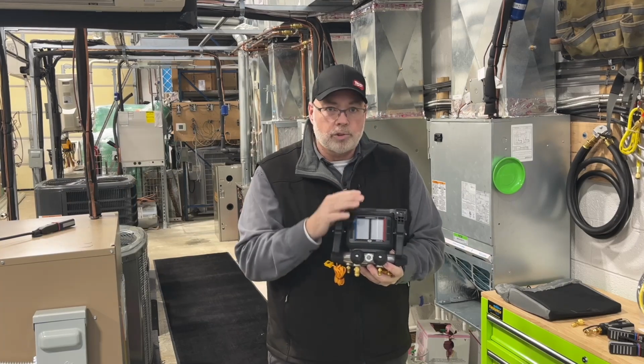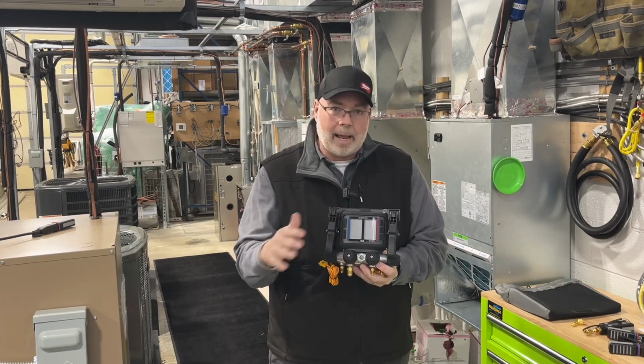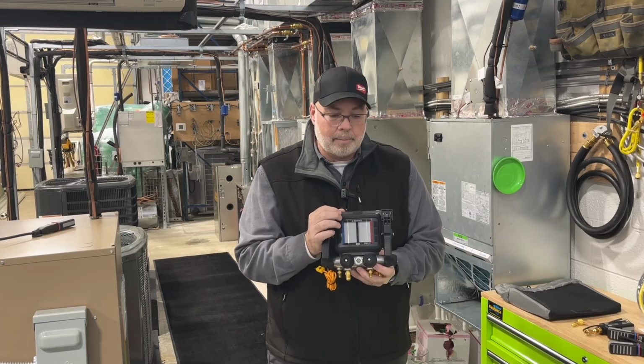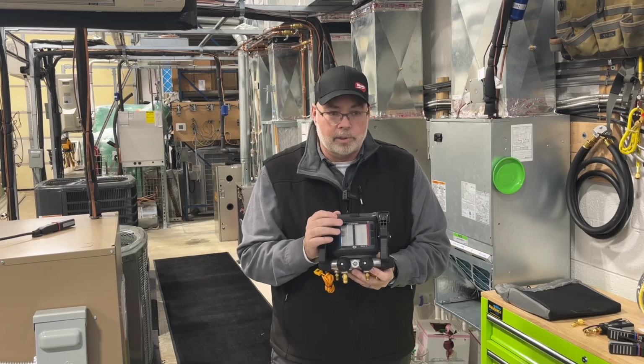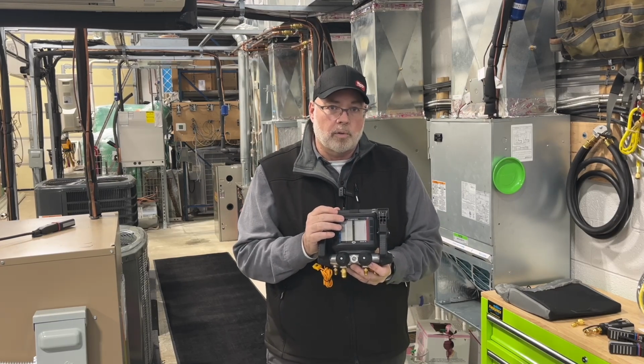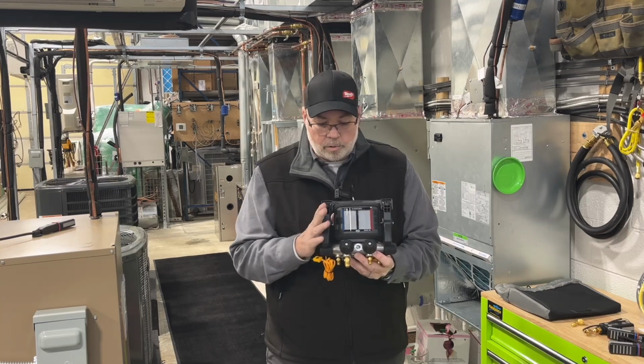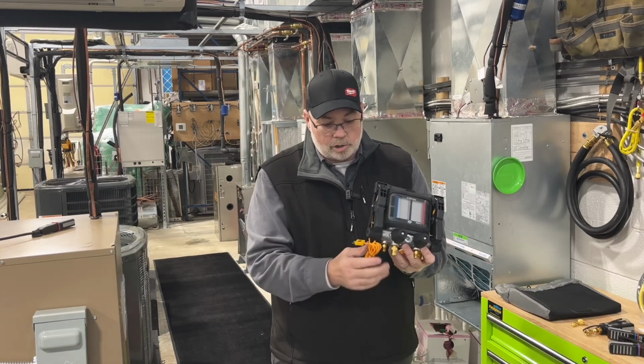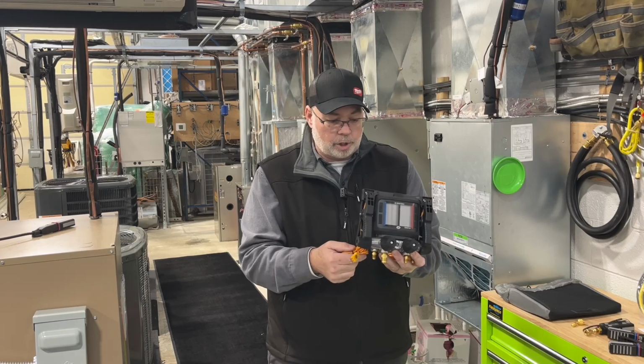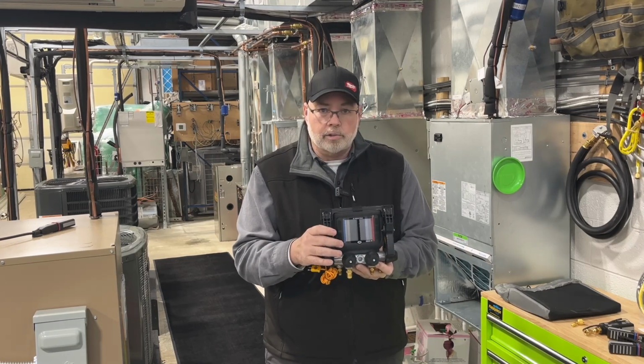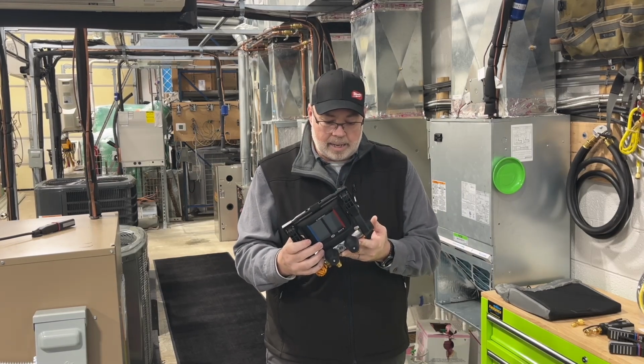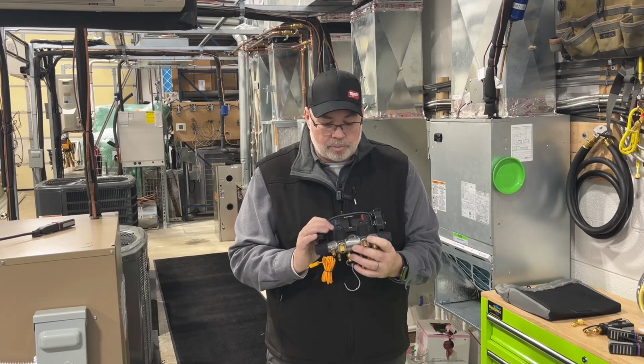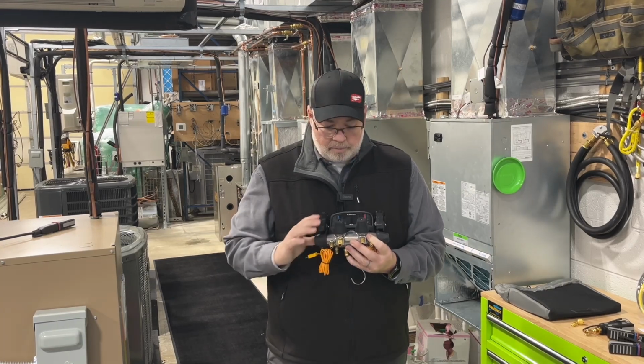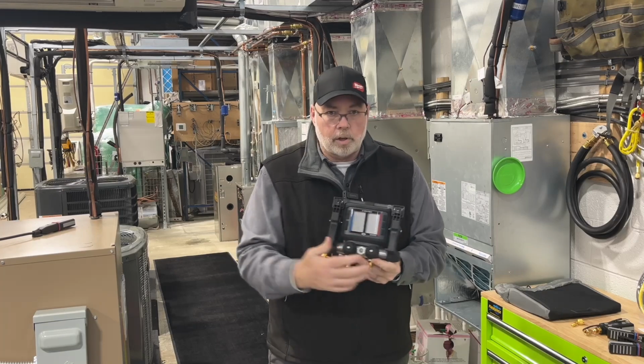And with all of these tools, they have a whole array of refrigerants already programmed in them, including the A2L refrigerants such as R32 and R454B. And this electronic gauge also has temperature clamps to be able to read your suction line and your liquid line temperatures. It has the 3/8 brute port for evacuation and the 4 valves.